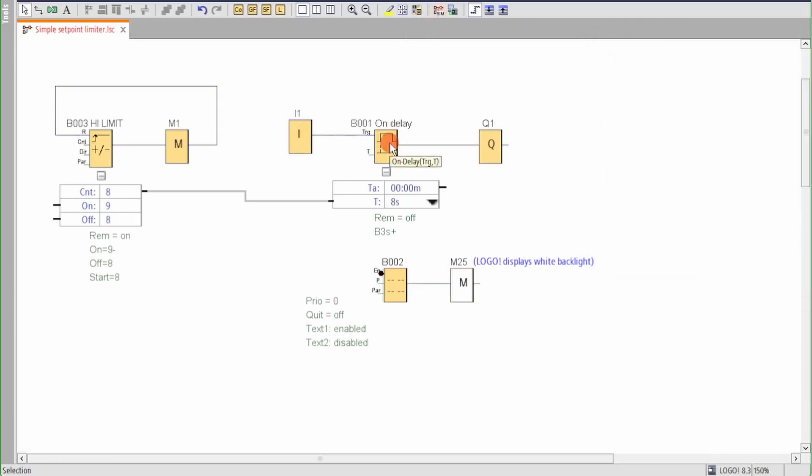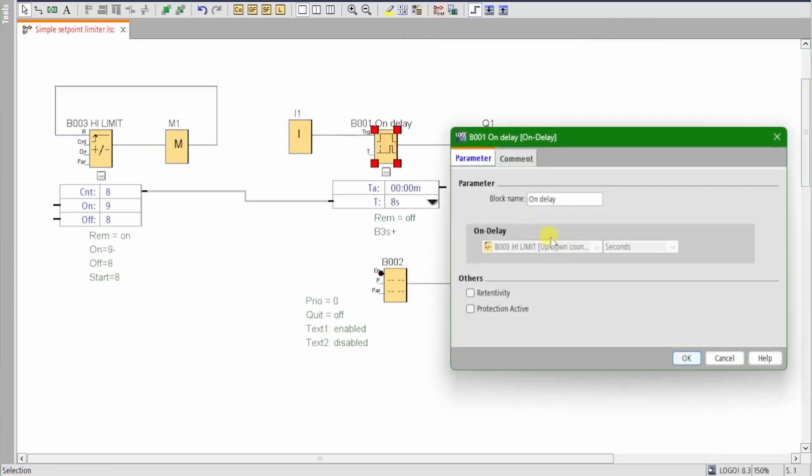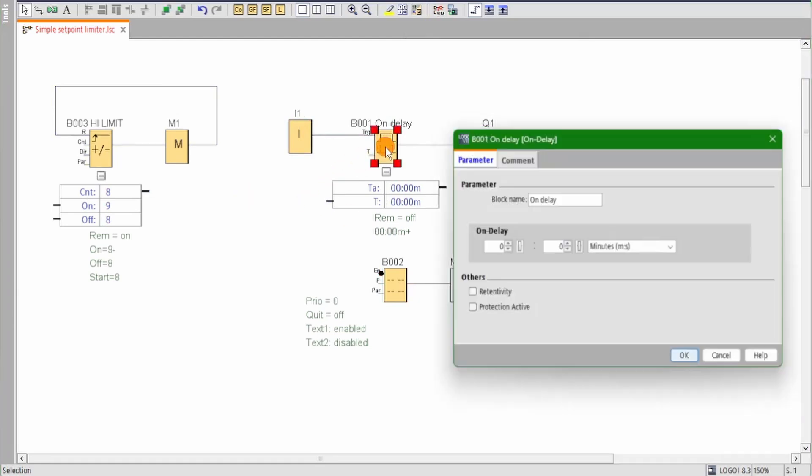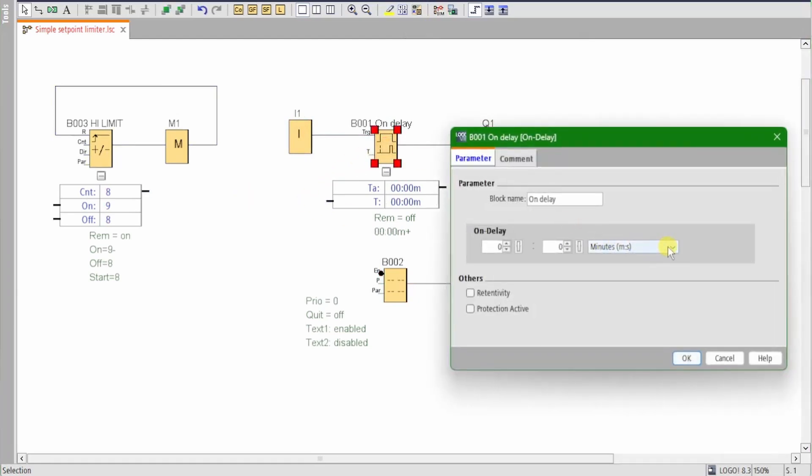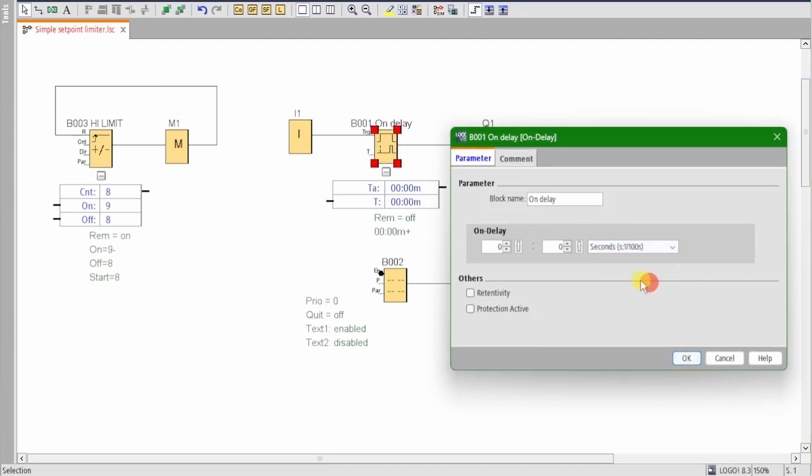When the timer has a referenced parameter, the timer's on delay units can't be changed. Deleting the parameter reference allows the on delay units to be edited. The parameter reference can then be redrawn. Here we're setting the timer to seconds and hundredths.